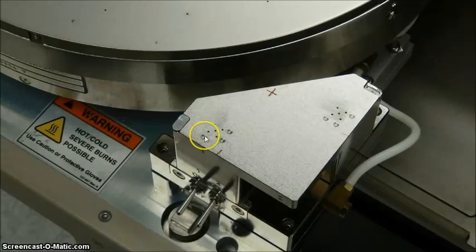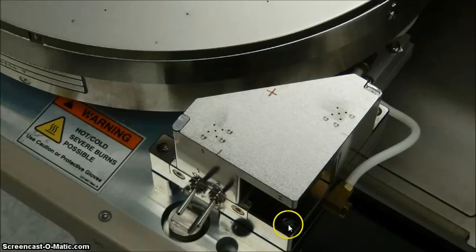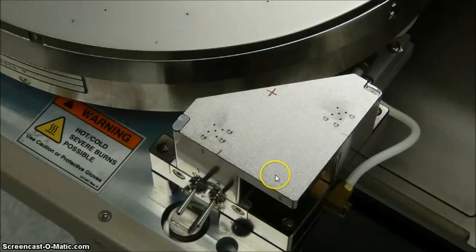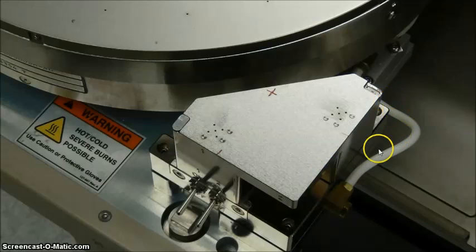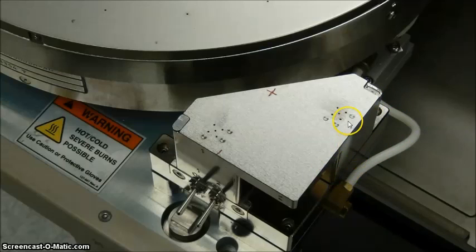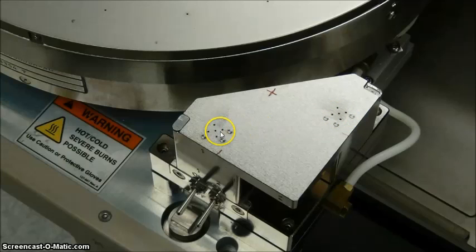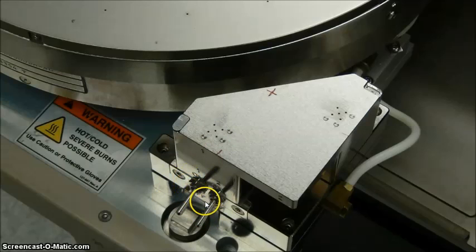It contains a simple leveling system incorporating three adjustable set screws, then the base is secured in place with one large center screw located under the surface of the chuck. Vacuum is ported to the aux chuck from the same line that feeds the main chuck vacuum. It is then routed to two switchable sites for temporary mounting of cleaning or continuity plates. The plates are roughly aligned using three raised alignment pins located at each site.